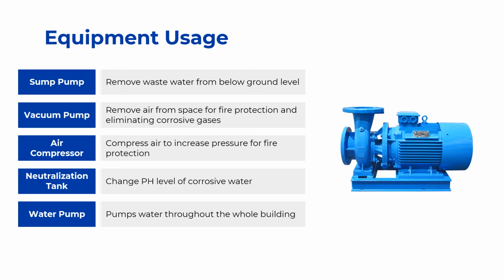Now, for the equipment used in the components of the plumbing and fire protection system, first you have the sump pump, which removes the wastewater from below ground level. Since drainage and sewage systems are usually based on gravity, anything below ground level needs a pump to pump it back up. Then you have the vacuum pump, which removes air from a space, either for fire protection to change the pressure, so as to avoid the fire going there, or to eliminate corrosive gases or any other materials.